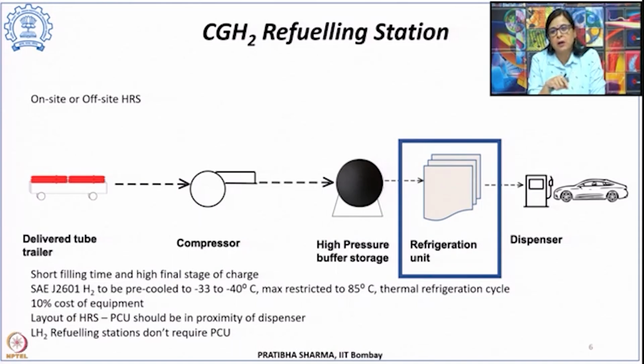and then the associated piping. When hydrogen is extracted from the high pressure buffer storage, before it is dispensed into the vehicle, it has to go through the chiller, where the coolant circulates through a heat exchanger, extracts heat from the hydrogen and then returns back to the chiller. In the whole process, the temperature of the hydrogen reduces to the range of -33 to -40 degrees centigrade.